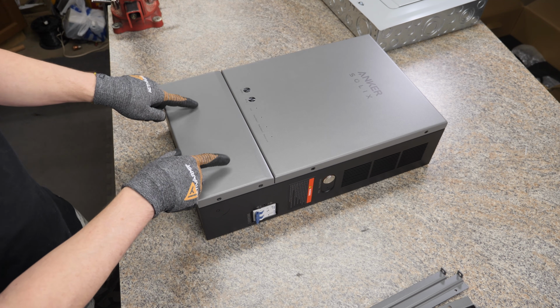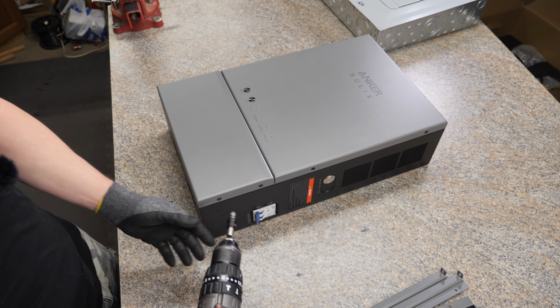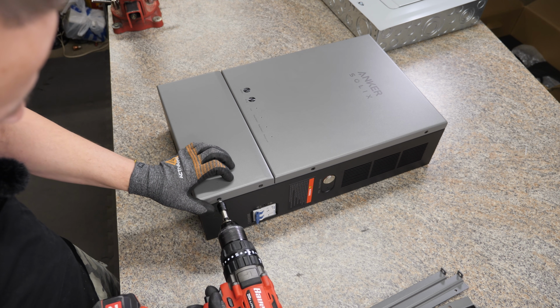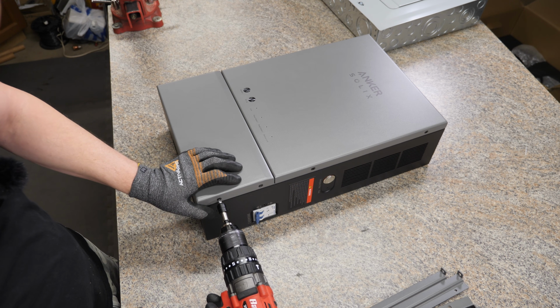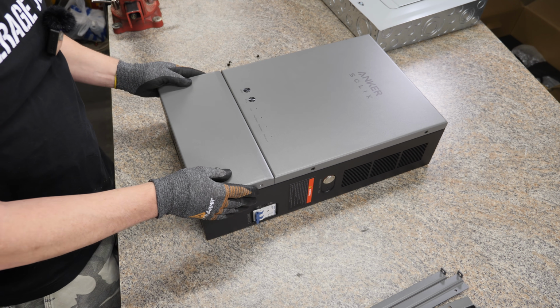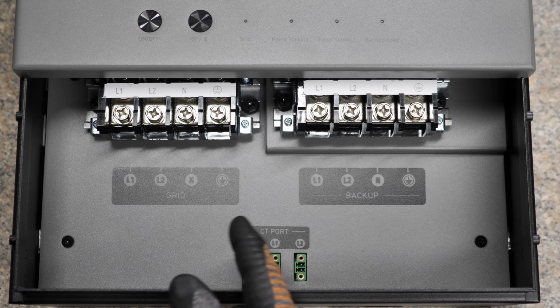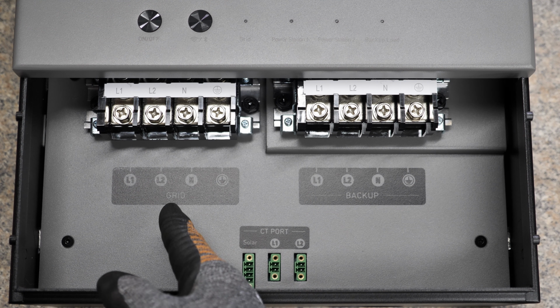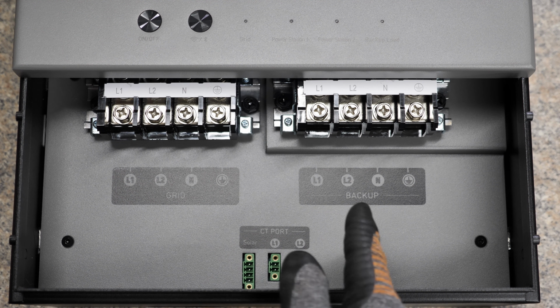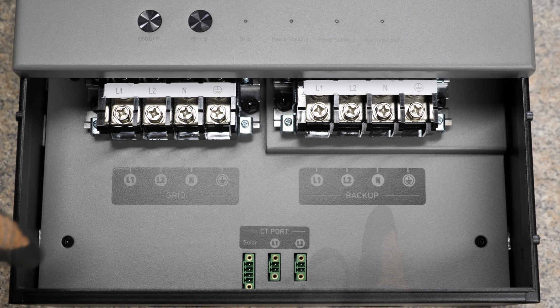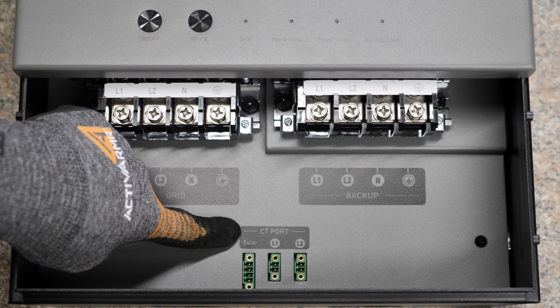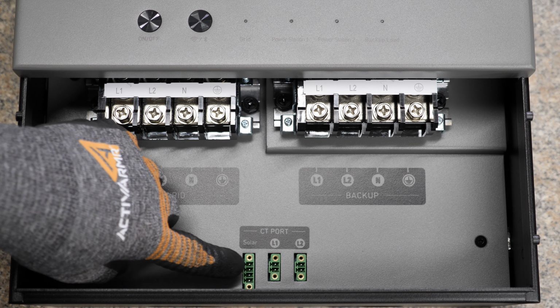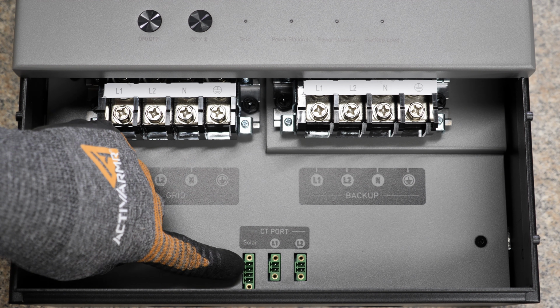Right here is a removable cover held on by 4 number 2 Phillips head screws. We'll take that off—this is where you connect all of your AC wiring, your grid input on this side and your backup loads on this side. Finally, right down here is where you connect your CT clamps, which I just showed you: L1, L2, and solar.